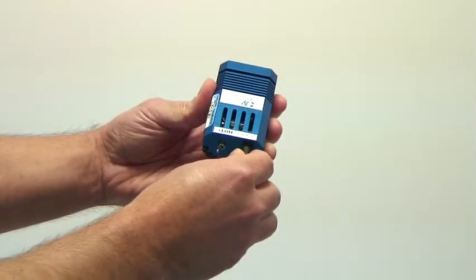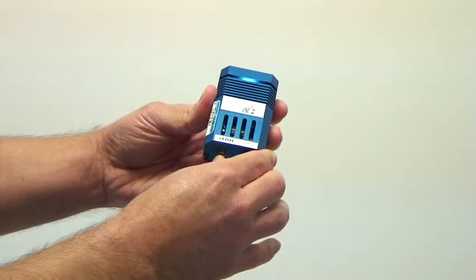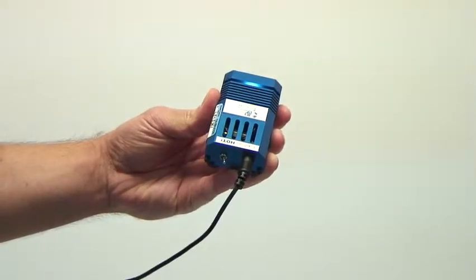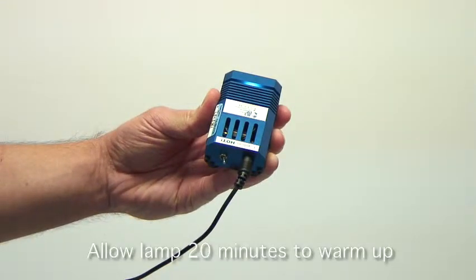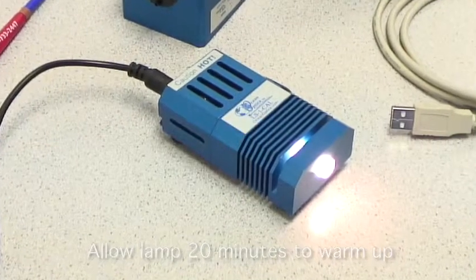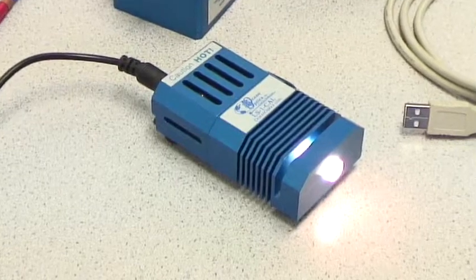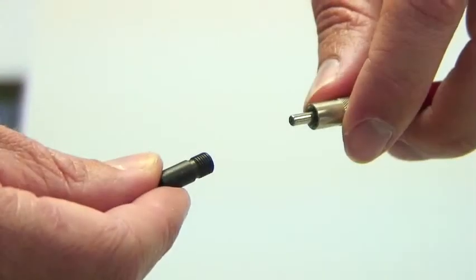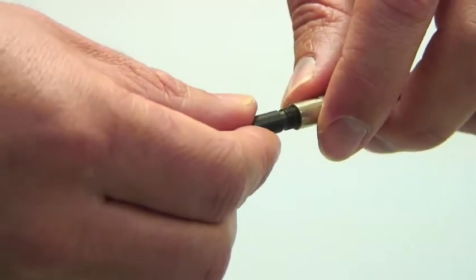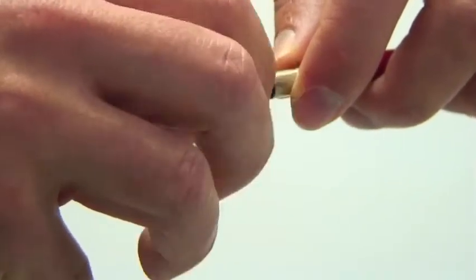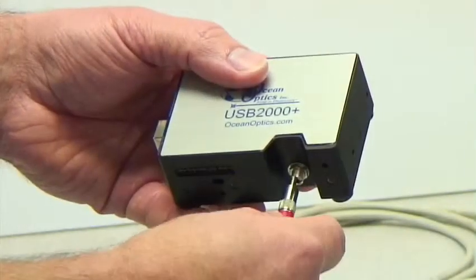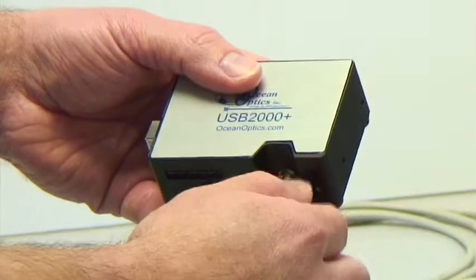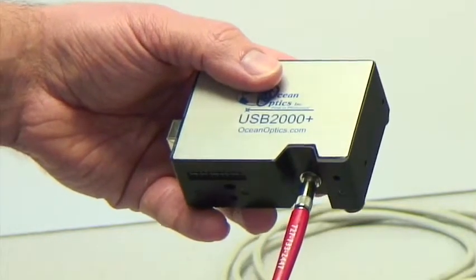First, you should connect the power to the light source and turn it on so that it can begin to warm up. For the LS1 Cal-INT, it is recommended to let the lamp warm up for at least 20 minutes. Next, connect one end of the patch cable to the bare fiber adapter. Connect the other end of the patch cable to the SMA connector of the spectrometer.